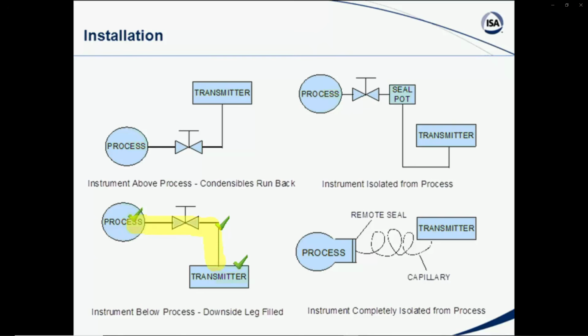But what that allows us to do is any vapors or bubbles formed will rise back up into the process. And this final situation over here, we actually deal with what's called a remote seal and a capillary tubing with our transmitter. And what we effectively are doing here is another form of isolation. The process is isolated at this point through the diaphragm seal.